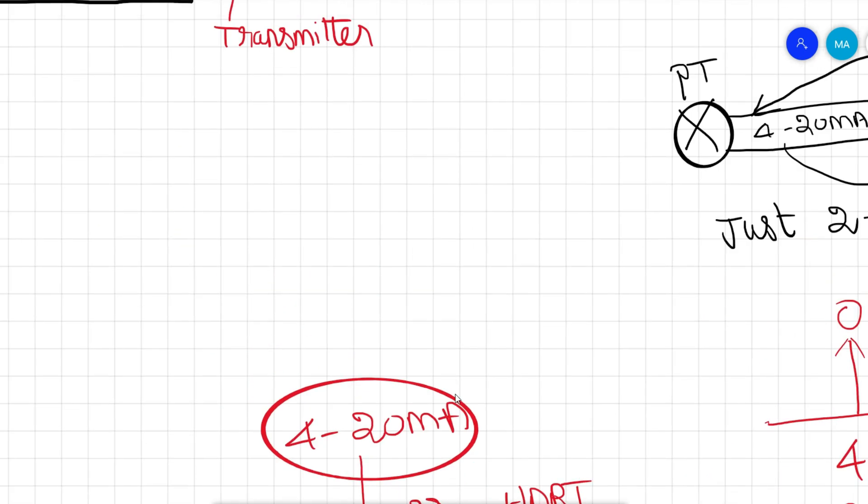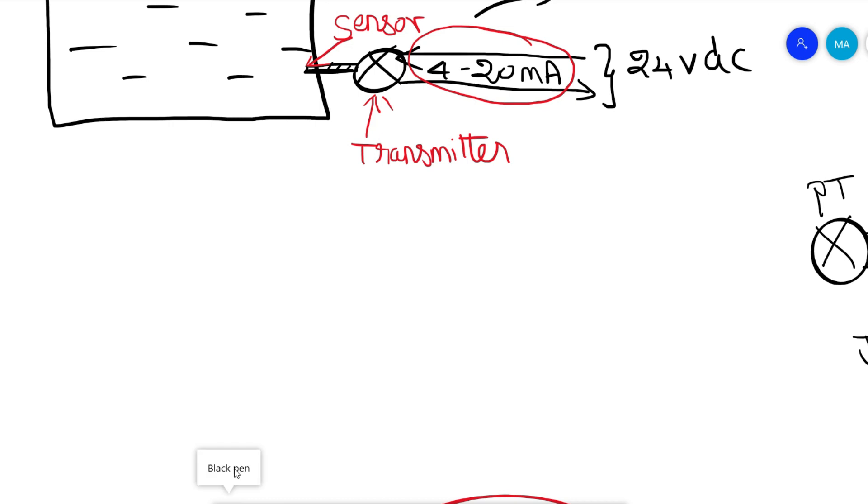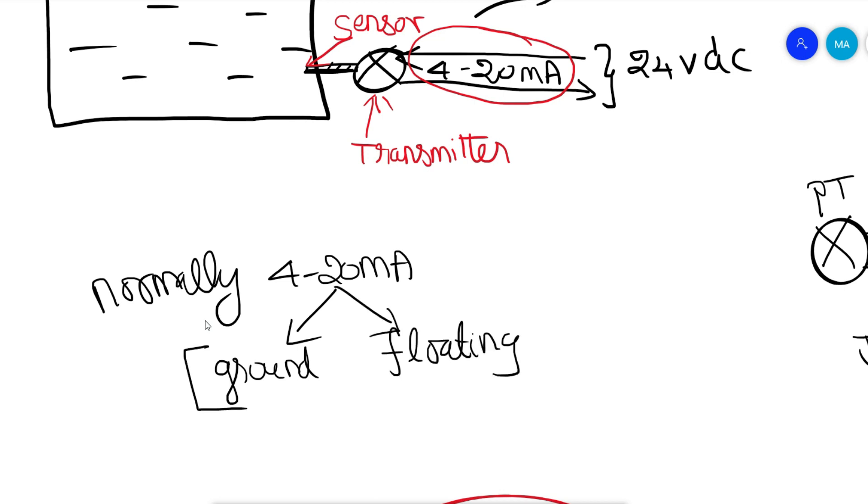Finally, two-wire 4-20 milliamps commercial instruments are isolated and floating, so ground loops and their associated errors and faults are relatively rare. This is the basic reason for 4-20 milliamps signal, which is widely and globally used in all process industries.